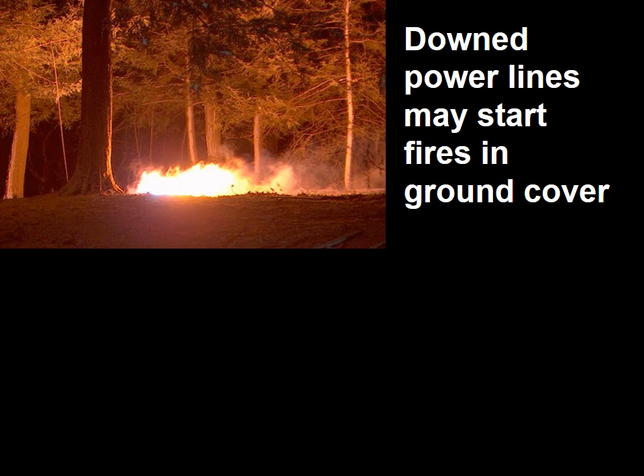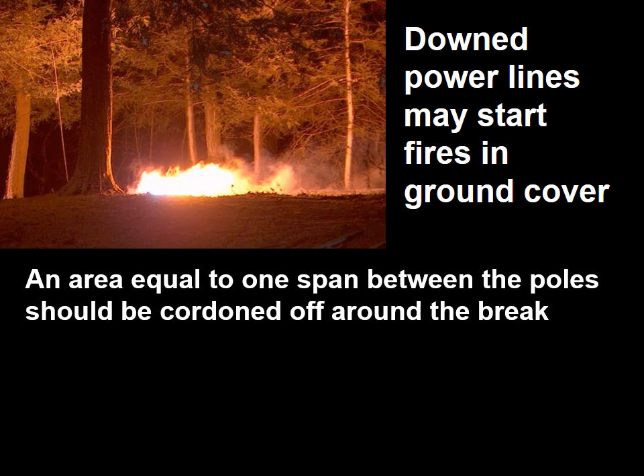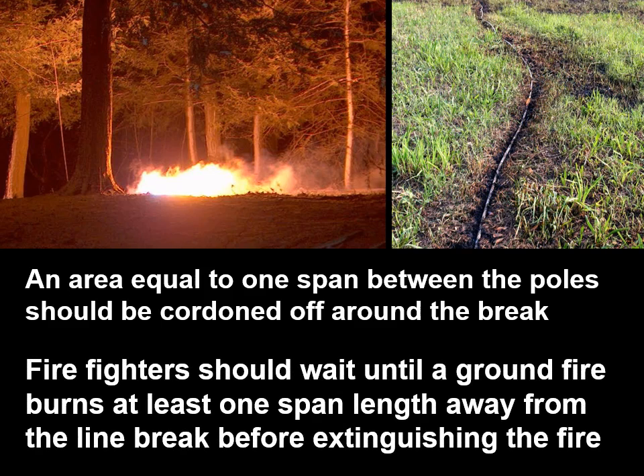Downed power lines may start fires in ground cover. An area equal to one span between poles should be cordoned off around the break. Firefighters should wait until a ground fire burns at least one span length away from the line break before extinguishing the fire.